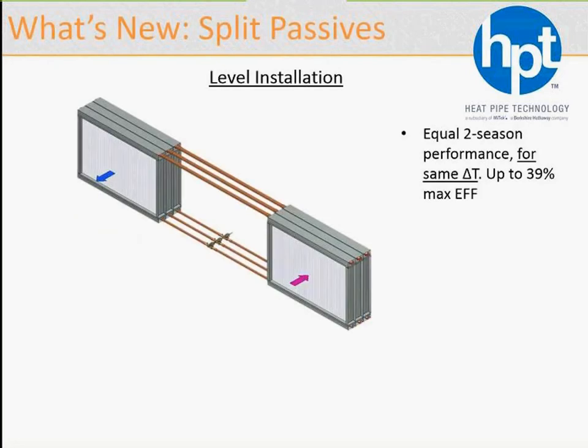Split passive. We show you here a system where supply and exhaust are on the same level, similar to our HRM, basically. This is a two-season recovery. Performance is average. You can get about 39% with 6 rows at 500 feet per minute. This is your typical system made up of 6 rows. Each 2 rows are headered into a vapor header up top and a liquid header on the bottom. And most have valves on the bottom to regulate the performance of this product, should you want to turn it off during economizer mode or to prevent frosting under severe winter conditions.